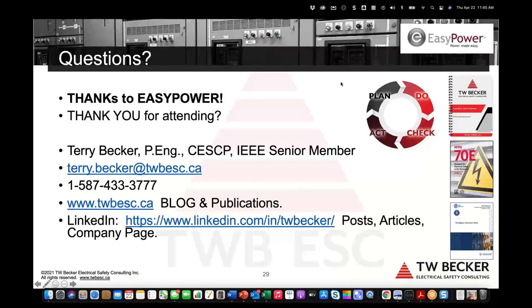that works the same as an 8.7 calorie coverall: a 50% probability of the onset of a second-degree burn injury if the worker is arc flashed at the ATPV. Plus, there's no documented evidence of any fatal injuries due to arc blast pressure in incident statistic reports. There's one available that the NFPA authored that is public domain, and it can be sent to you if you want it. If you're not aware of it, we can follow up on that offline.